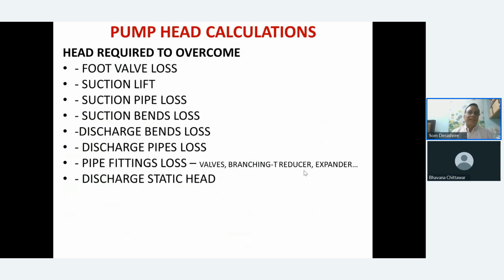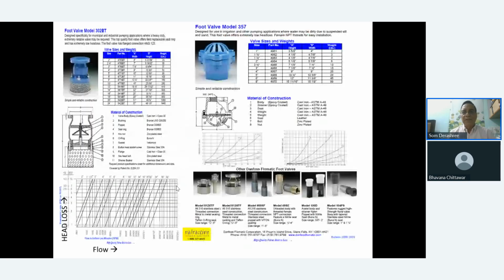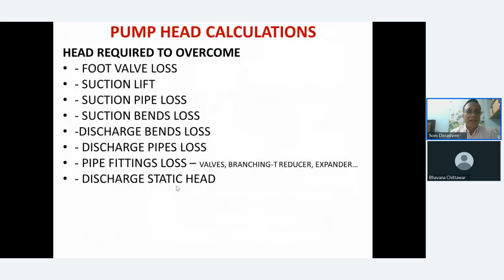Now, pump head calculations. The head required to overcome the foot valve losses, suction lift, suction pipe losses, suction bend losses, discharge bend losses, discharge pipe losses, pipe fitting losses, and of course, discharge static heads. All this has to be overcome by the pump. So let's take them one by one.